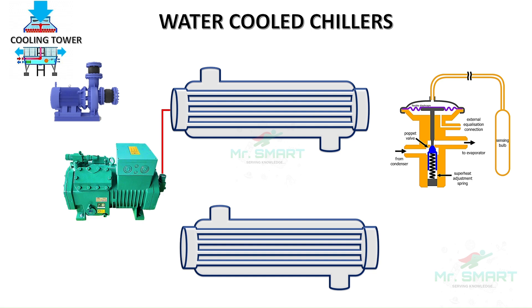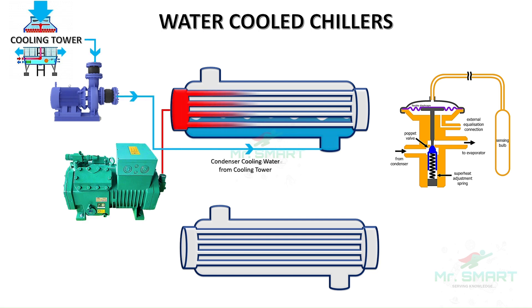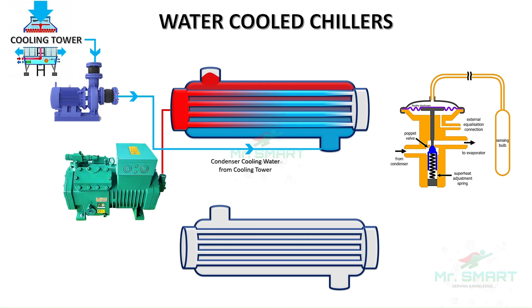Similar to the air-cooled chiller, the low-pressure refrigerant is compressed into a high-pressure, high-temperature refrigerant in the compressor and passed to the condenser. In the condenser, the refrigerant releases heat to the water, which is then cooled in the cooling tower. A cooling tower is a special setup that releases heat from water to the atmosphere through evaporation. The hot water from the condenser is cooled and pumped back to the condenser through condenser pumps.